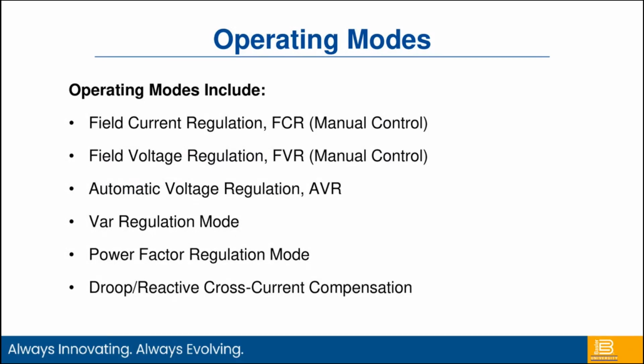There are multiple operating modes. The very basic is manual control. Primarily, we're going to use field current regulation, or what we call FCR mode. What that does is the voltage regulator doesn't care about the output. So with what I just told you about the voltage and current output of the machine, if I'm in FCR mode, the voltage regulator doesn't care. It is strictly regulating the field current, the amount of current it's putting into the exciter field. We can do this exact same operation, except rather than looking at current, we can do voltage, and that's called FVR mode. Both of those are manual type control operations. These are good in situations when you're trying to troubleshoot, if you want to check your sensing configurations to make sure everything is correct, you have the proper phase rotations, things like that. So it's a very helpful tool, but not typically the mode you're going to operate in normally.